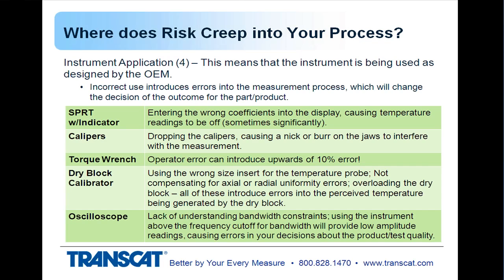And if that is left at the old coefficient values, or the wrong coefficients are plugged in, or the probe is changed out without changing those coefficients, you're going to get incorrect temperature readings, and you're going to make wrong decisions about your product or your process. A set of calipers. Those are easily picked up and moved around and possibly dropped, and if you have nicks or burrs on the jaws, that's going to shift your zero or possibly affect your readings.